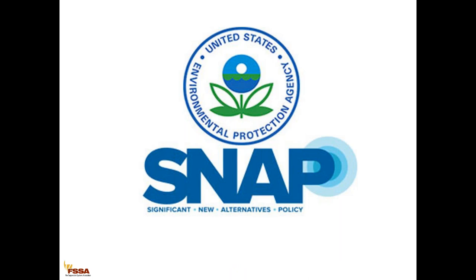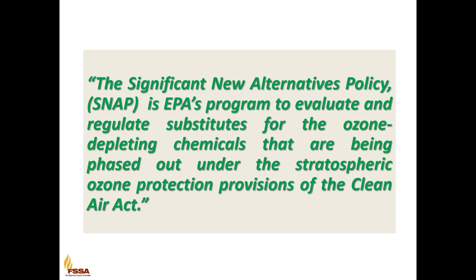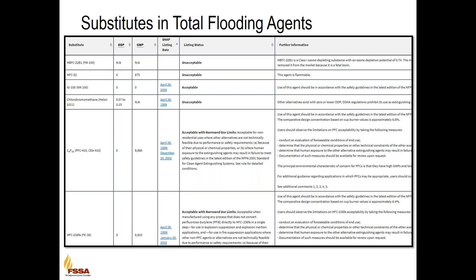At about the same time, the EPA created the SNAP list. SNAP stands for Significant New Alternatives Policy and is still in use today. The EPA website defines SNAP as EPA's program to evaluate and regulate substitutes for the ozone-depleting chemicals that are being phased out under the stratospheric ozone protection provisions of the Clean Air Act. Any fire suppression agent created to replace halon has to receive approval from the EPA's SNAP list prior to being commercialized. That is, this is the current, most up-to-date SNAP list for the total flooding halon 1301 replacements and serves as only an example. The full list can be found on the EPA's website.